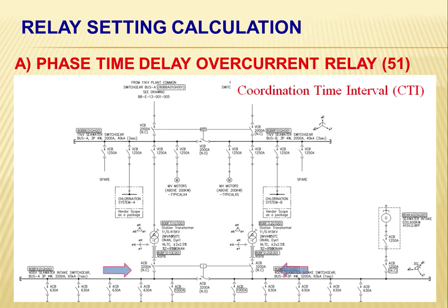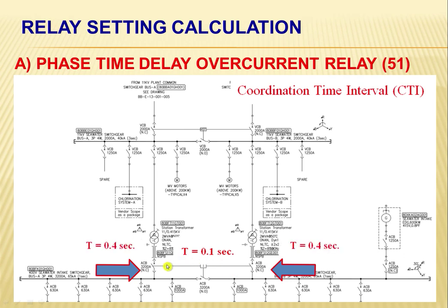Okay, so here, this is our subject breaker, wherein our relay is connected, for both the incomer of LV switchgear. This is for bus A and for bus B. We have here for our bus coupler, the time delay assigned is 0.1 second. Here, this breaker, the subject of our discussion, we have assigned the time delay of 0.4 second. Upstream, we have here 0.70 second.